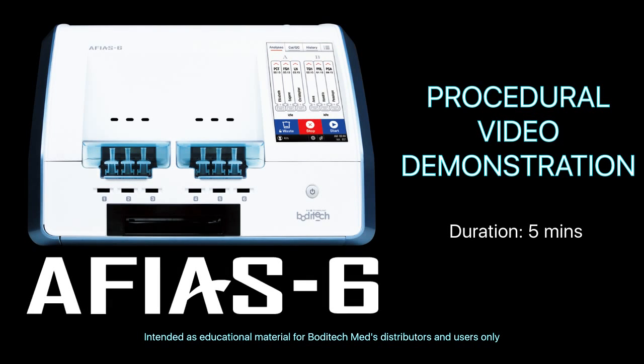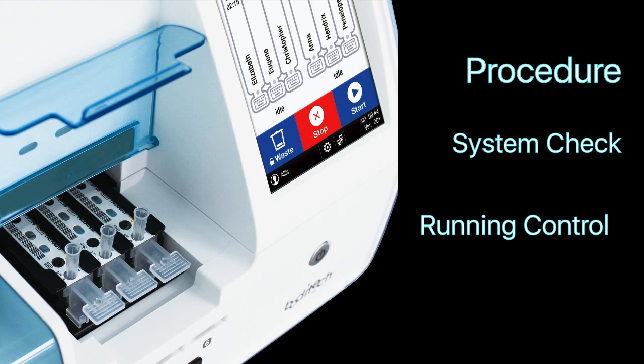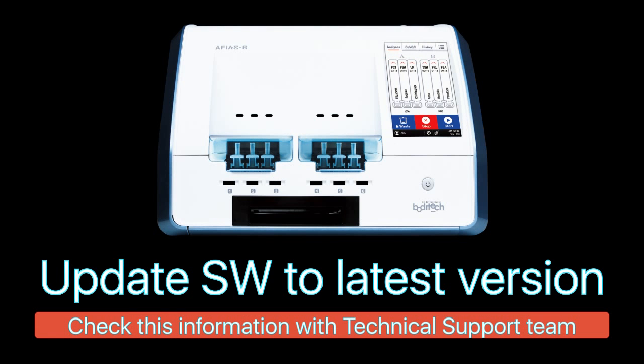This video will demonstrate the procedure on how to run the system check cartridge, two level controls, and two level calibrators in AFIAS-6. It is highly recommended for users to update the reader software to the most recent version available beforehand.